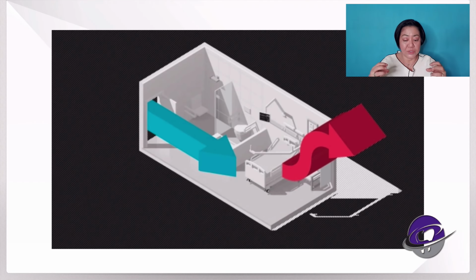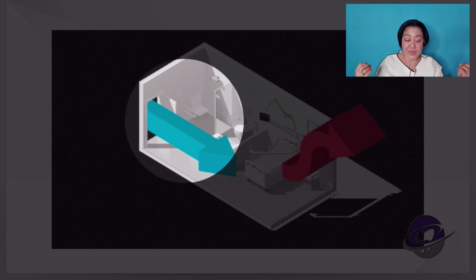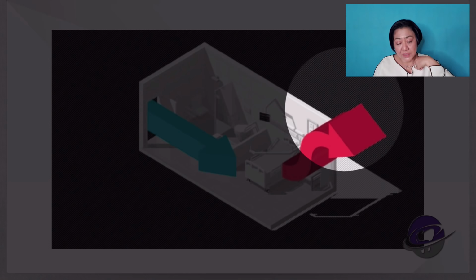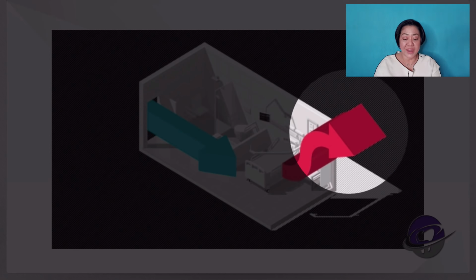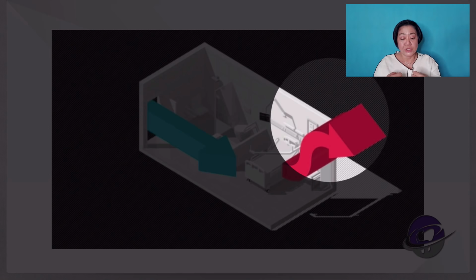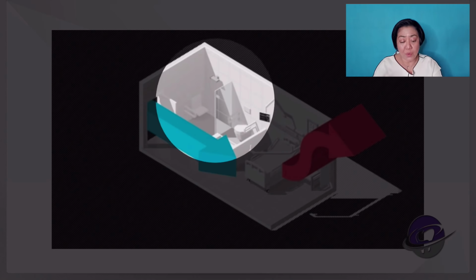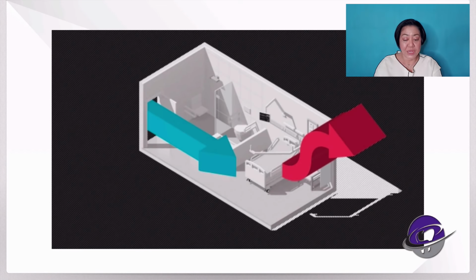Now, however, the challenge about this is that in order for the rooms to maintain negative pressure, the windows cannot be opened and the doors close automatically. But most of all, these rooms need to spit out 30% to 40% more air than they are taking. So there is only a one-way flow of air. So again, you have to ask yourself certain issues. Where do you get the clean air?